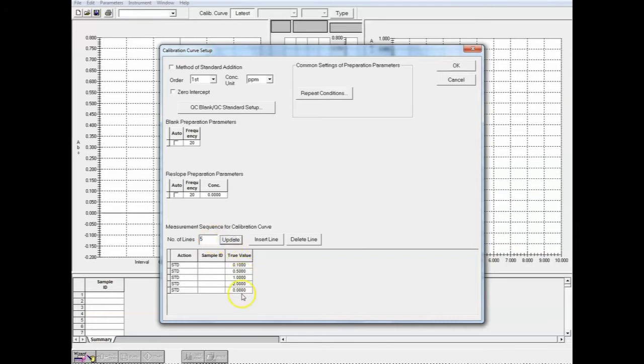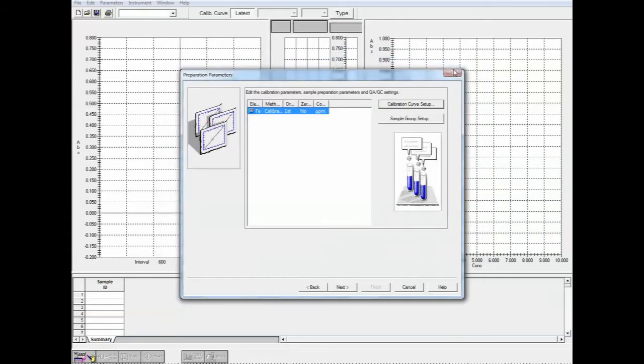Okay, so you can see now it added a line down here. And we're also going to tell it the value of our standard, so what the actual concentration is in ppm. We're going to change that to 1, because remember our standards were 1, 2, 3, 4, and 5 ppm. So we're going to change these to match up with what our standards are. And this will vary depending on what standards you actually use. So if you make up different concentrations, you can enter in whatever you actually use. Okay? So we've told the machine what our standards are, what the concentration of those standards are, so it's going to use that when it calculates the calibration curve. So we're going to say OK to that.